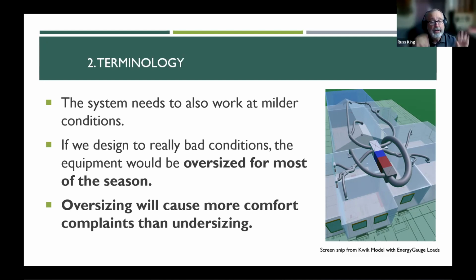So when it gets to a certain point, it shuts off. That's what your thermostat does. Your thermostat says, oh, that's enough, stop. And then it turns back on, and then it stops and then it turns back on. We call that short cycling. If your air conditioner is oversized, it's going to short cycle. It's going to run for very short periods of time, and it's going to blast cold air in for very short periods of time. And when it does that, it causes stratification, it causes cold spots, it causes warm spots, it uses a lot of energy, it shortens the life of your equipment, okay?